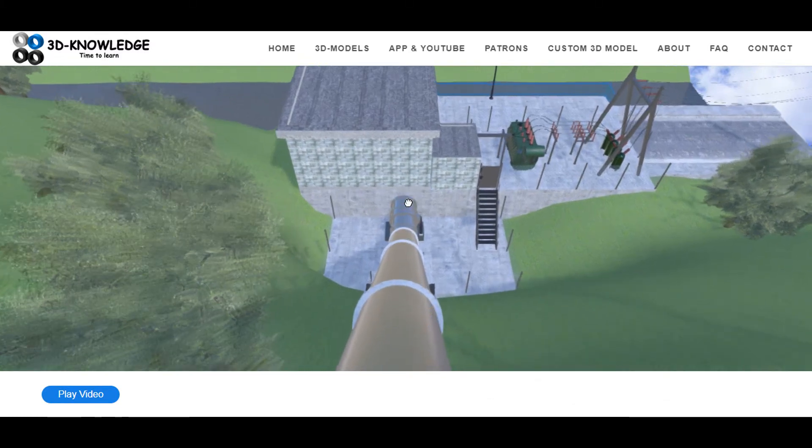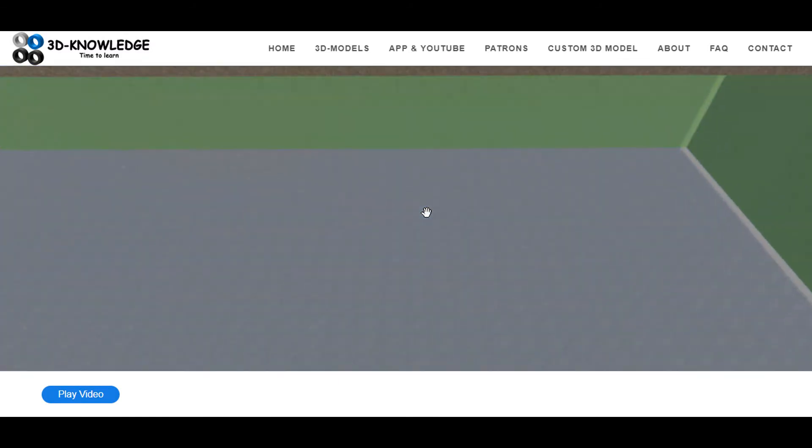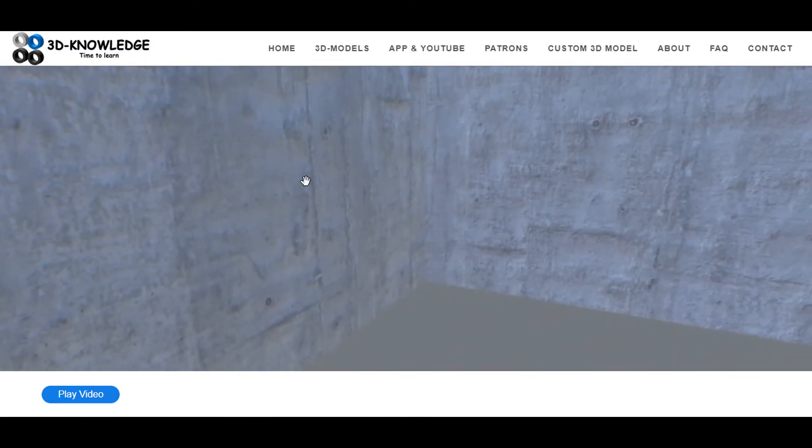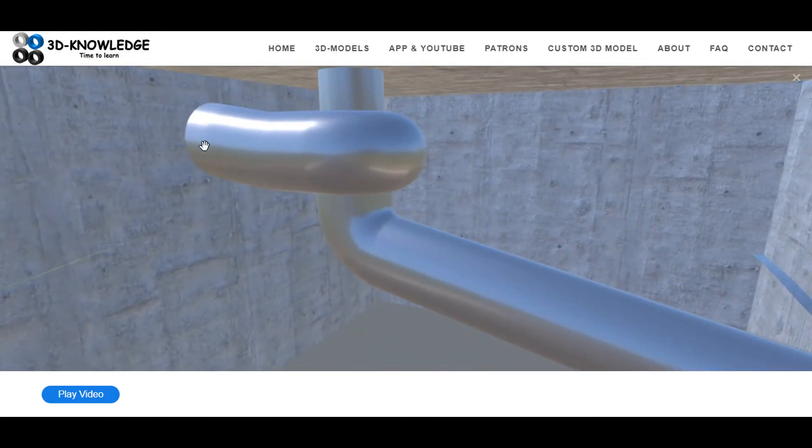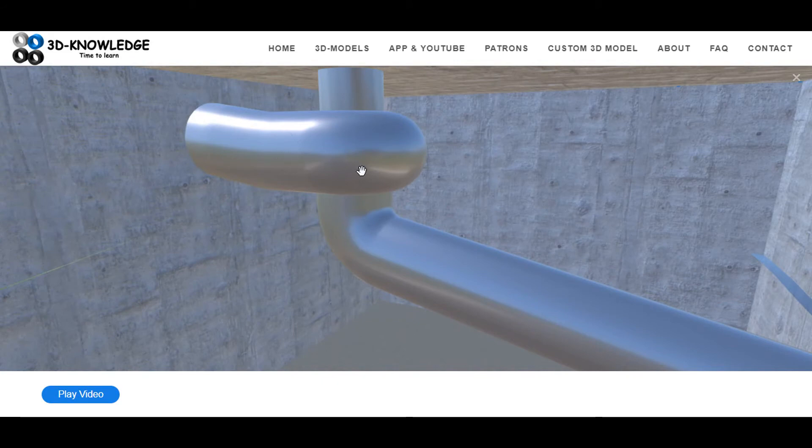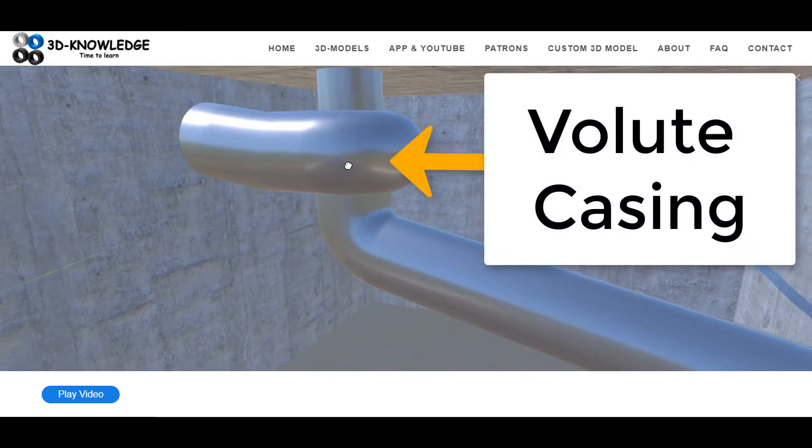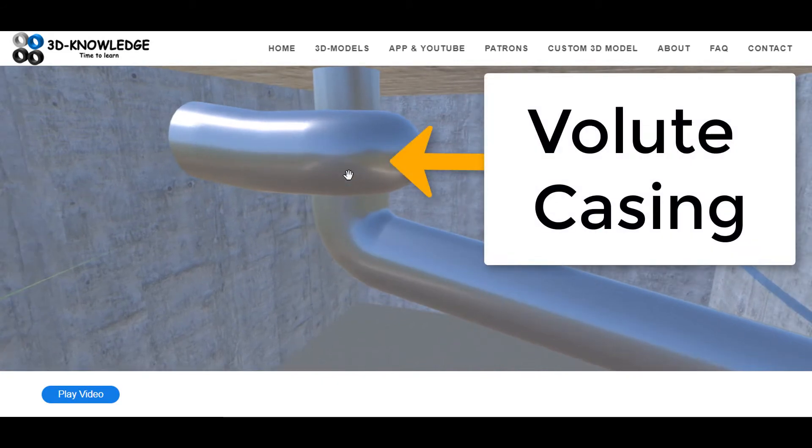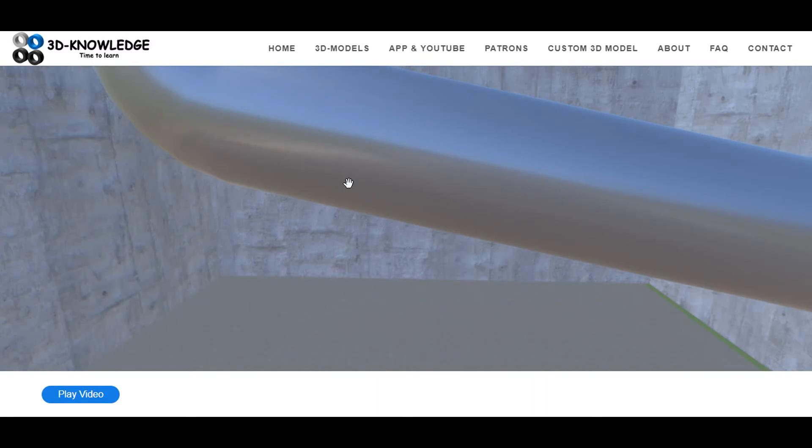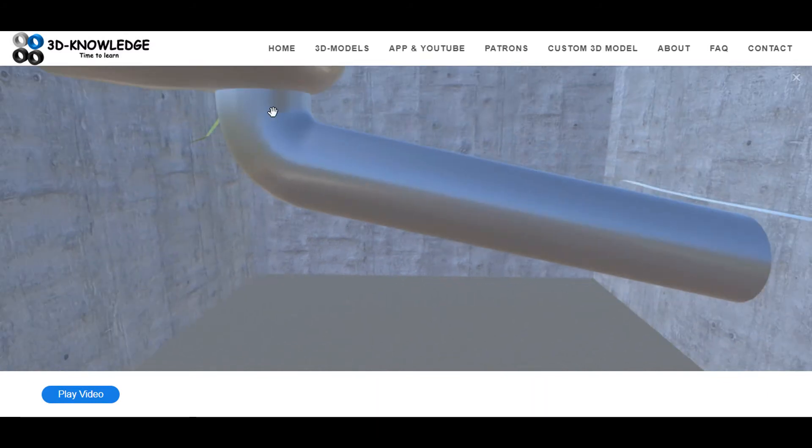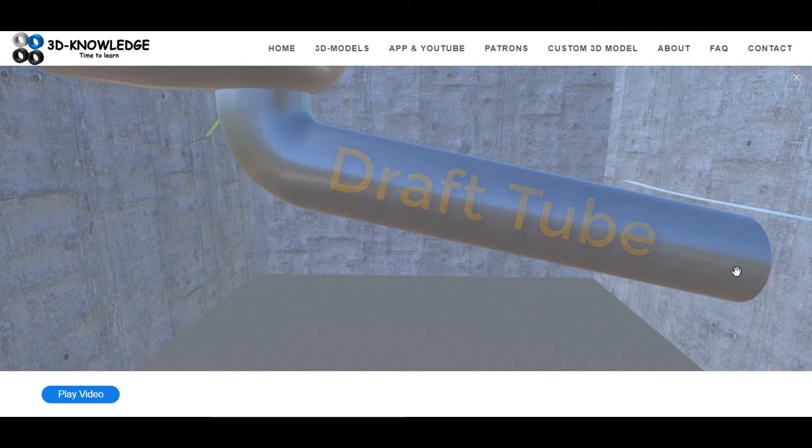We'll follow the penstock under the power station and it will lead to the turbine. The water comes in here, goes into a volute casing, and then drops out the bottom along this pipe here and out. This pipe is known as a draft tube and the water exiting out of the draft tube is known as the tailrace.